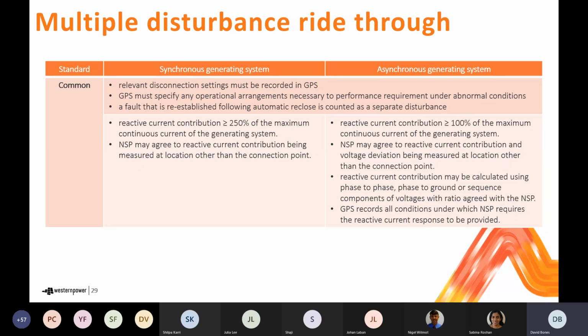So as part of the post-event analysis, attention was turned to the question of whether or not performance standards should actually specify a requirement to be able to ride through a number of faults in succession, and if that was the case, how that criteria should be specified. And so a fair amount of work went on, and a multiple disturbance ride-through criteria was developed and implemented within the national electricity rules on the east coast of Australia. In developing the requirements that now exist within the WEM rules and are proposed to go into the technical rules, we've drawn heavily on that learning from the east coast. So this first slide presents the common requirements that exist for the multiple disturbance ride-through GPS. I'll step through those, and then we'll look at the ideal and minimum requirements.